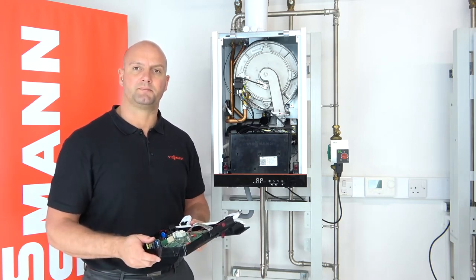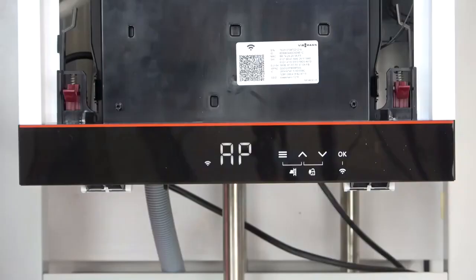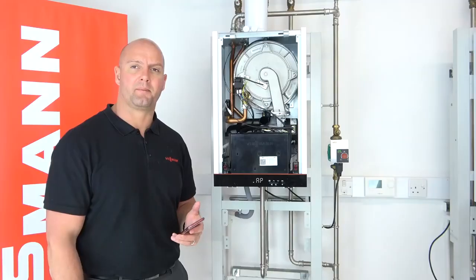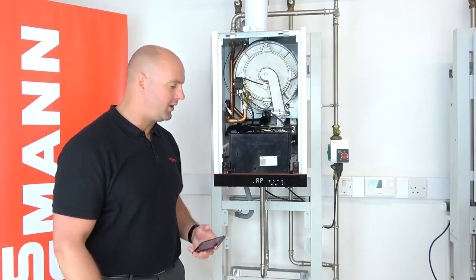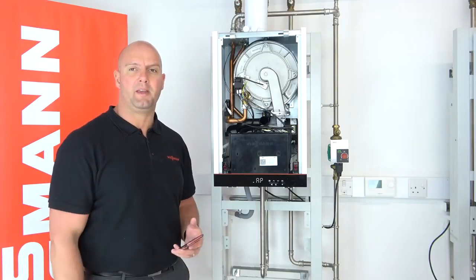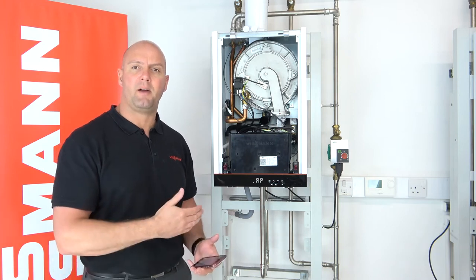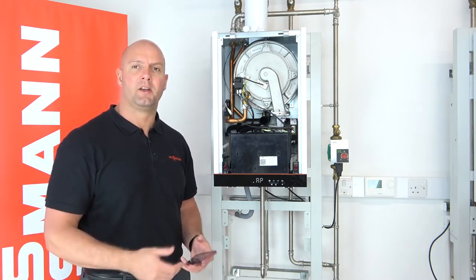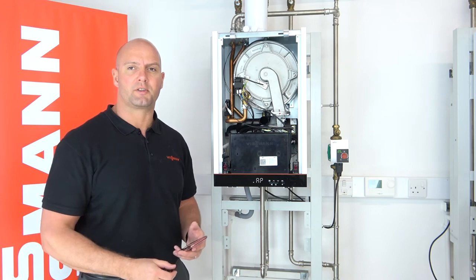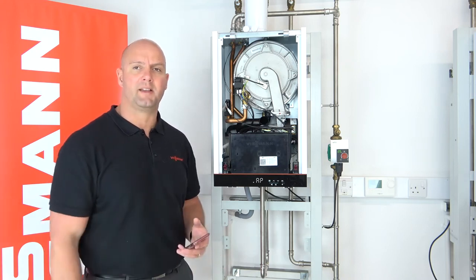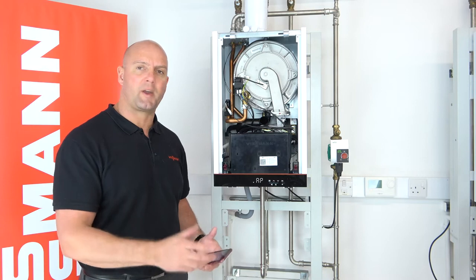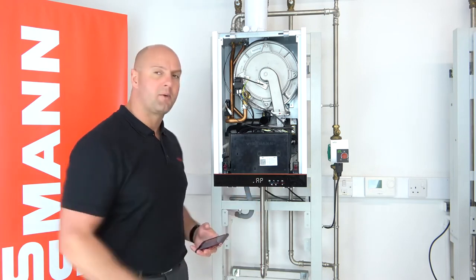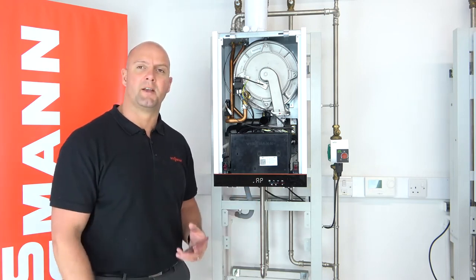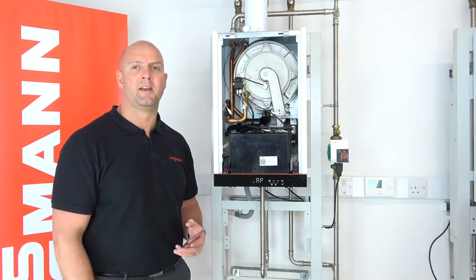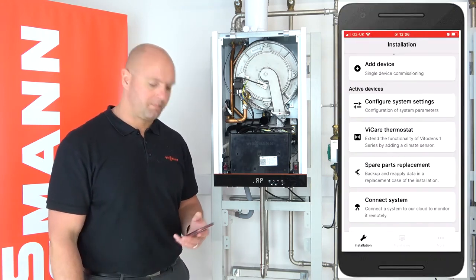So we've now swapped the PCB over physically. It's now time to commission the PCB using the ViGuide app. As you can see on the front of the boiler, it already comes up with AP mode. If you accidentally take it out of AP mode, we do have videos on our YouTube installer channel on how to put the boiler back into AP mode. But just as a quick overview, we press the menu and OK buttons together for 4 seconds, go to B5, press OK, and then the boiler's back in AP mode.